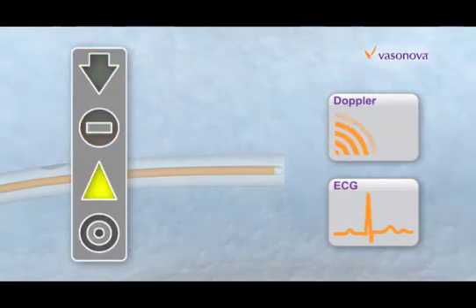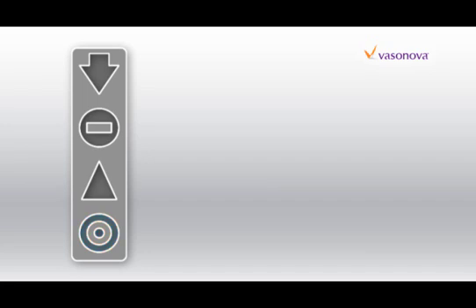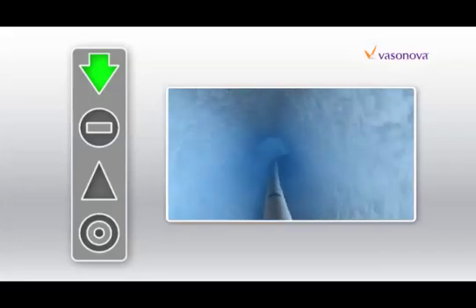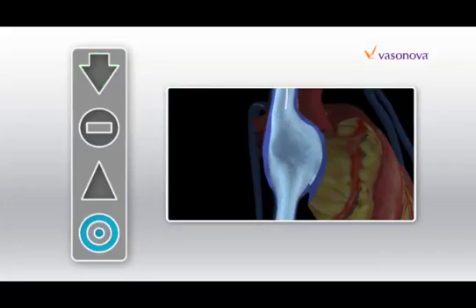The green arrow indicates the catheter tip is moving with the blood flow towards the heart as appropriate. The blue bullseye indicates the tip has arrived in the lower one-third of the superior vena cava or at the caval atrial junction.